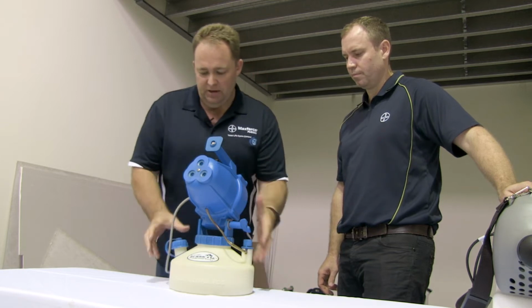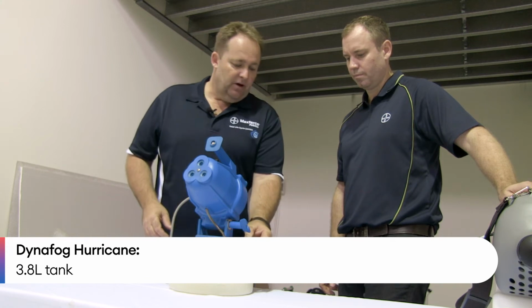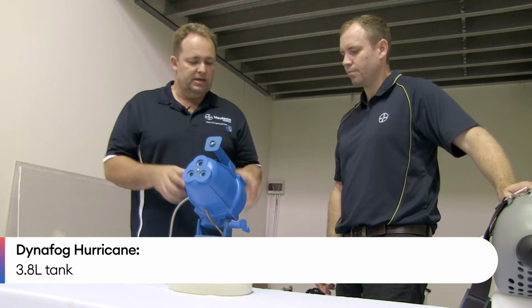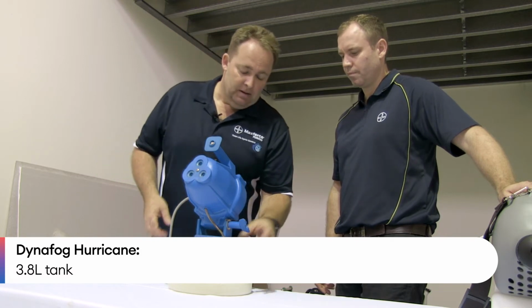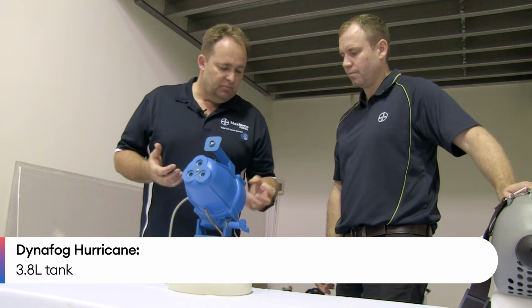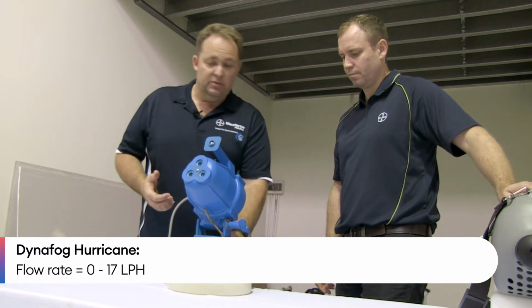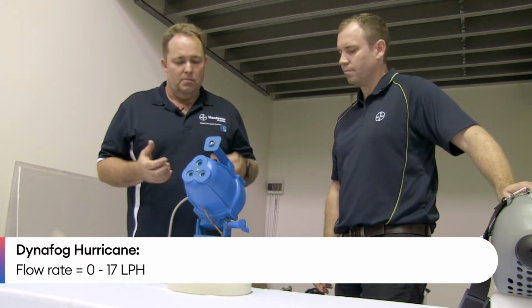And we've basically got a tank at the bottom that we fill up with our solution, and we have a flow mixing valve coming out of that tank. That's picked up via Venturi, so a lot of the other technology that's available pressurizes the tank and pushes the fluid out. This actually draws it out through a Venturi. Lot simpler technology, not as precise. With this particular machine, we have 3 settings, and we have almost infinitely variable on the Vector Fog. And that allows us to set the size of the droplet coming out of it.